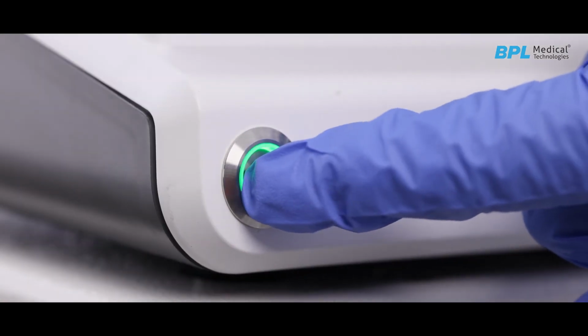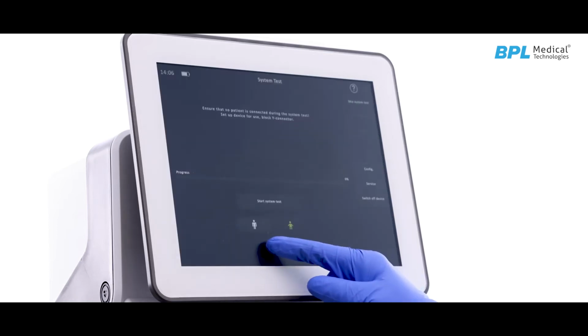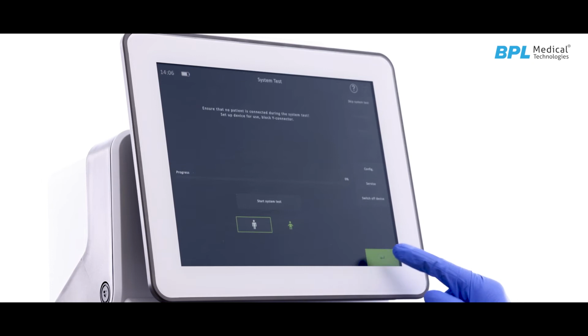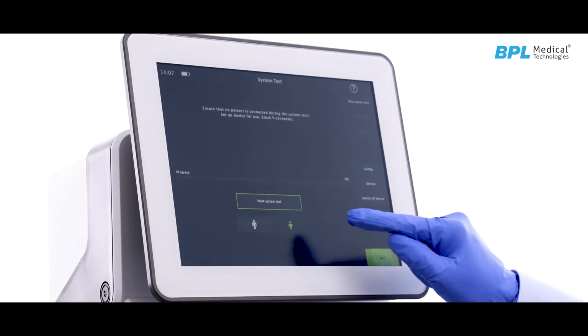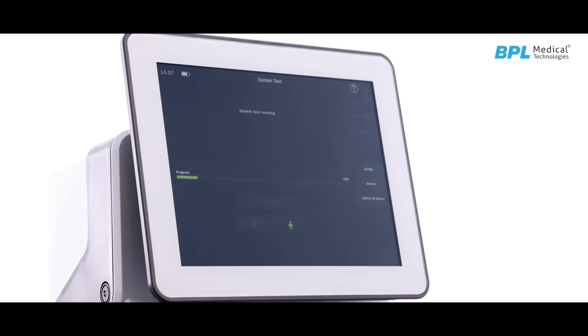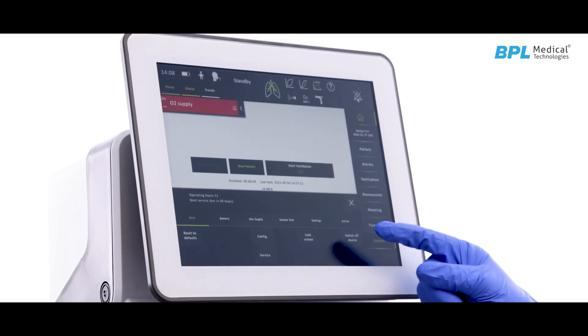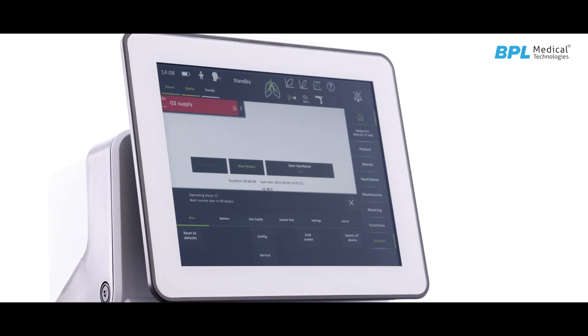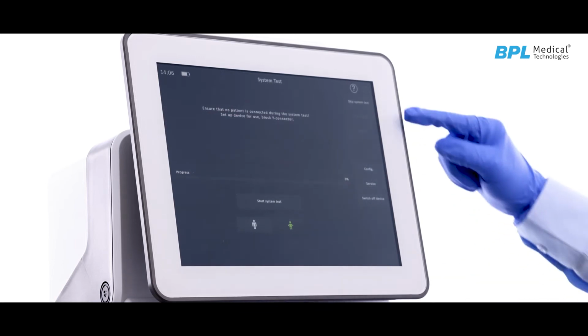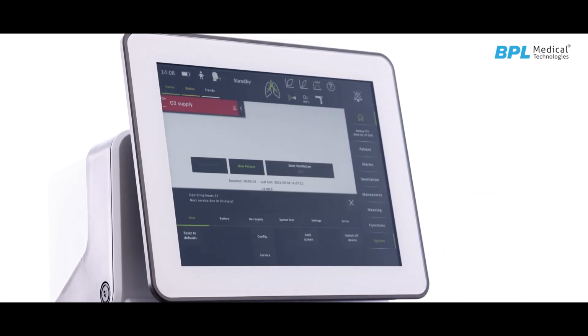Press the master control switch to switch on the device. The unit will boot up with the power test and will ask you to select between adult and pediatric patient category. After selection, a system test is needed to do a complete self-test, including proper assembly of the breathing system, functioning of all sensors, power supply voltage, etc. Once all the self-tests are successfully completed, it will enter the standby page. At the end of each test, a confirmation of test pass with the test result will be displayed. In case of an emergency, the user can select skip test, enter the standby mode and start the ventilation.